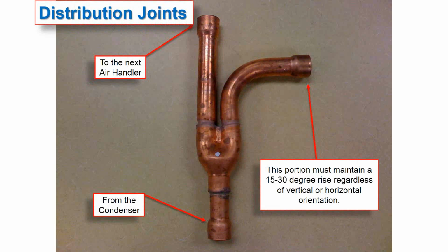This is a look at our distribution joint. These distribution joints are used for connecting our indoor units for heat pump systems. What we do is we pipe from the outdoor unit inside the building, and when we want to pipe to multiple indoor units, we use this joint. This termination is going to pipe to one indoor unit, and this termination here is going to allow us to pipe to the next air handler. So from our condenser to our next air handler to one room for the first air handler here.